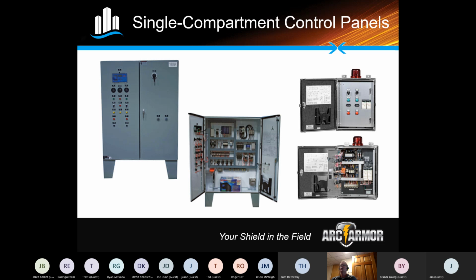Here are typical wall mount type panels. These panels will range from what they call a NEMA 1 or a NEMA 12 panel, which is like this one right here. It's just cold rolled steel painted gray. There's also what they call a NEMA 4X panel, which is stainless steel more times than not in our industry. It can also be fiberglass, but it's designed to be installed in corrosive or outdoor applications. And the stainless steel versions can come in 304 or 316 stainless steel.